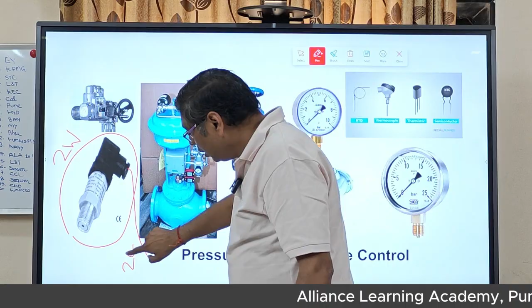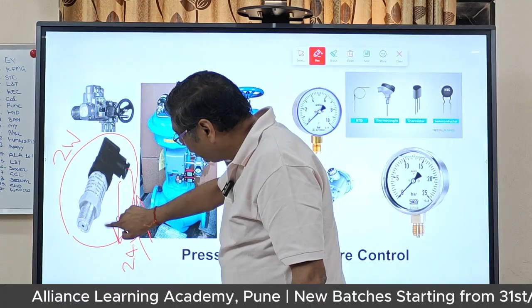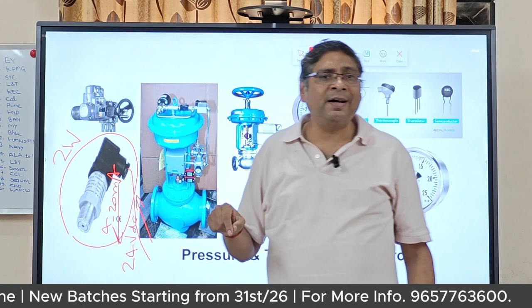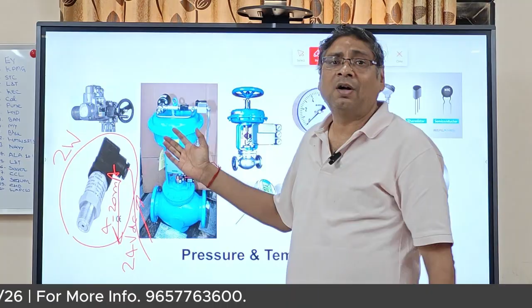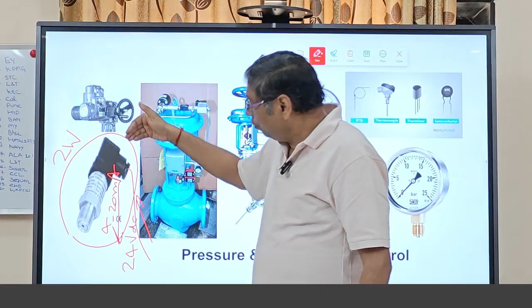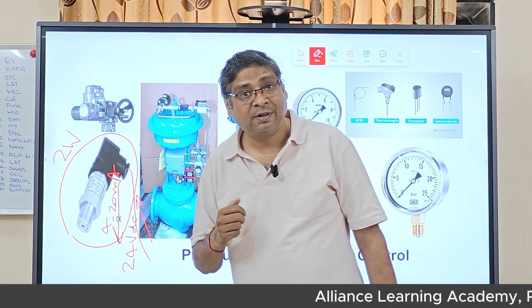Why? Because we are giving here 24 volt DC, and it is giving back over that 4-20 milliamps. After this class you will have hands-on with this, so you understand what is the 24 volt, how the connection is done, and how 4-20 is coming back. That's why I'm saying it's a 2-wire transmitter.